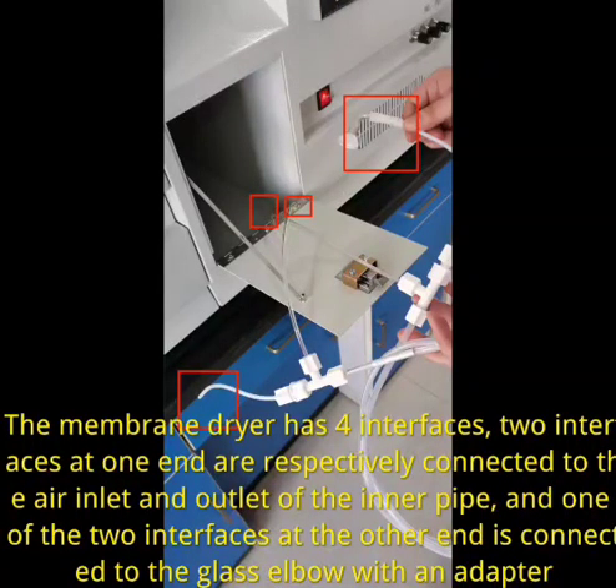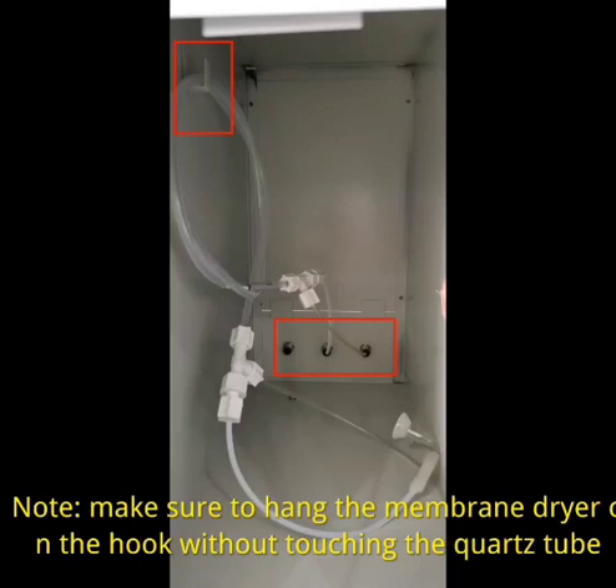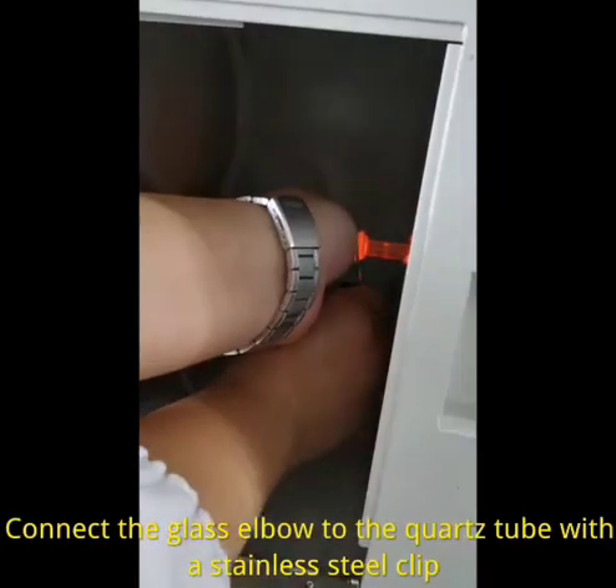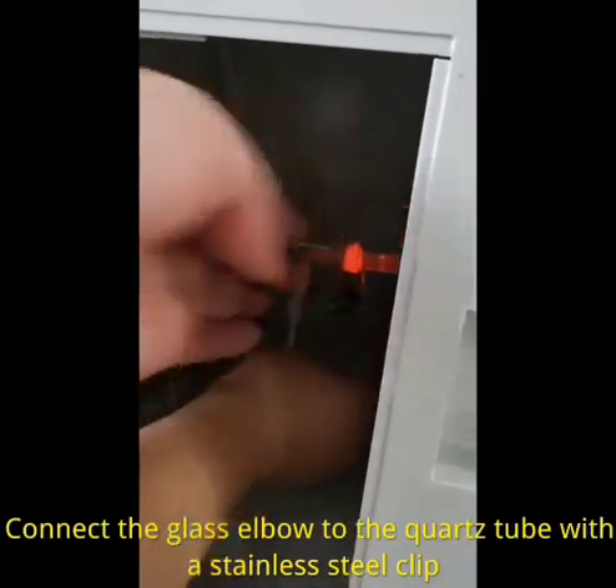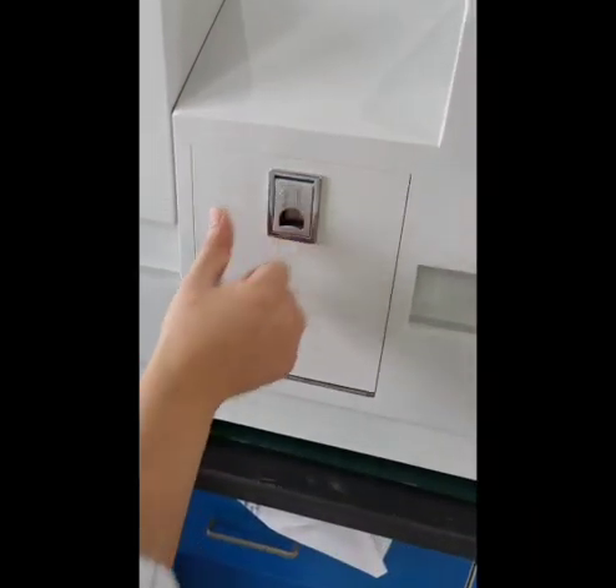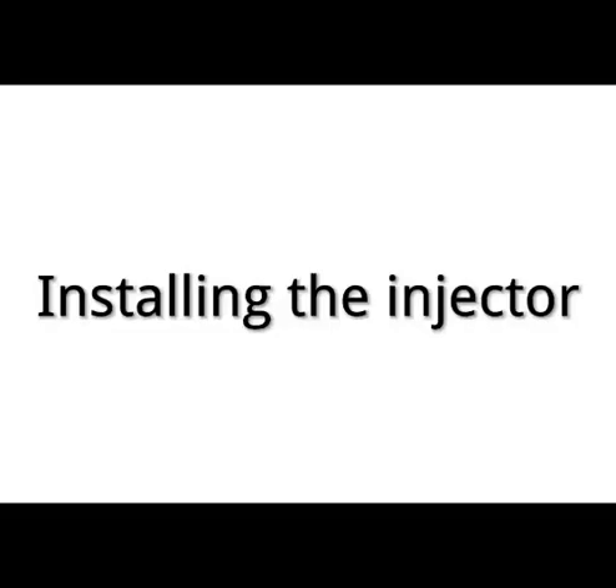Installing the membrane dryer. The membrane dryer has 4 interfaces. 2 interfaces at one end are respectively connected to the air inlet and outlet of the inner pipe, and one of the 2 interfaces at the other end is connected to the glass elbow with an adapter. Note: make sure to hang the membrane dryer on the hook without touching the quartz tube. Connect the glass elbow to the quartz tube with a stainless steel clip. Close the cover. Installing the injector.